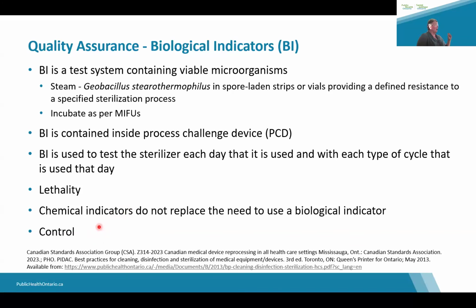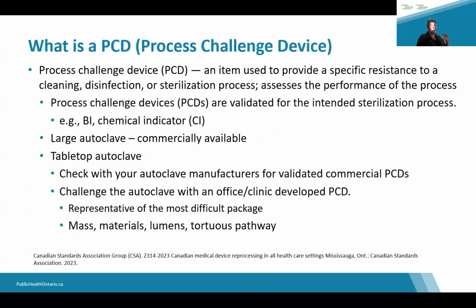So you take your BI and its control from the same lot number of BIs and you incubate them at the same time under the same conditions. So that's your biological indicator. It's really important that you run this because when we assess a lapse, we're always asking, did they do their BIs? What were the results of the BIs? It's important to know that your sterilizer has the ability to kill the organisms.